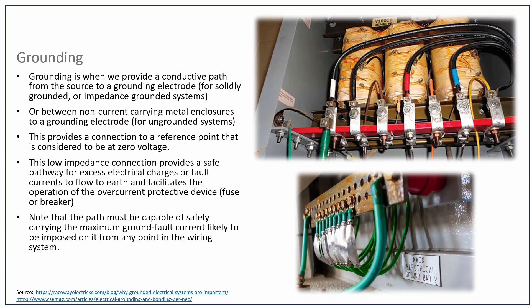The path must be capable of safely carrying the maximum ground fault current likely to be imposed on it from any point in the wiring system. So there's a minimum size for grounding conductors, obviously based on the fact that this is our main thing that keeps our system safe — it has to have a lot of current carrying capability and be sized properly. We'll talk about how to size those later on. Right now we're just talking about the terms grounding versus bonding. Grounding is essentially providing a reference to earth.